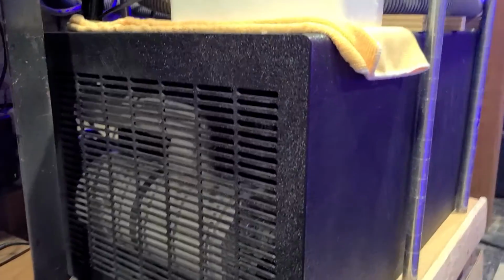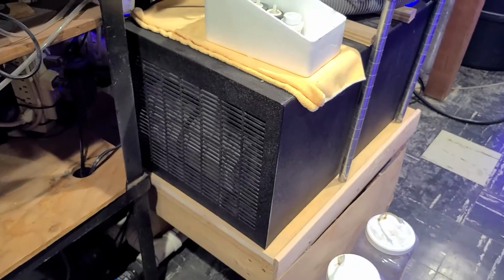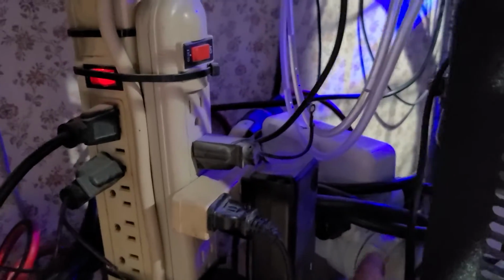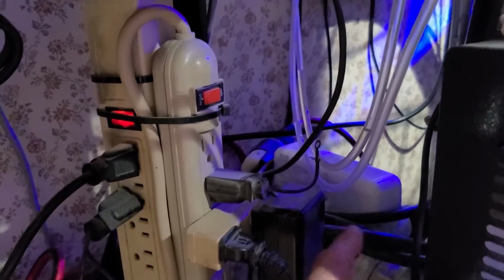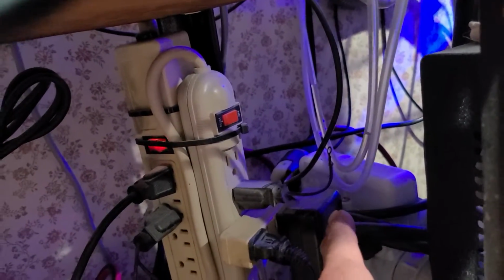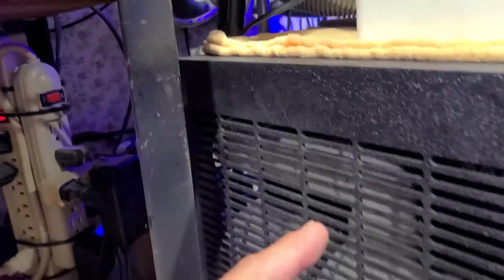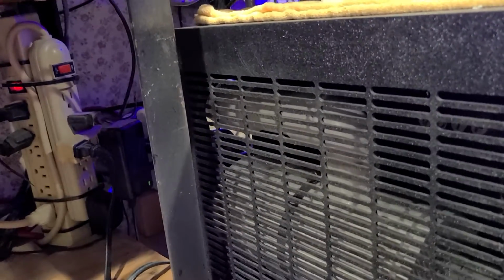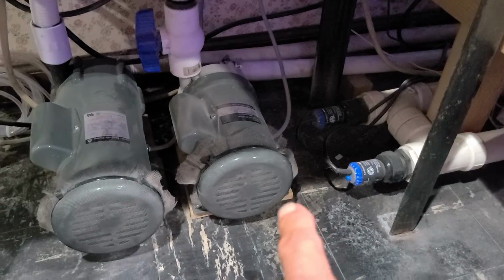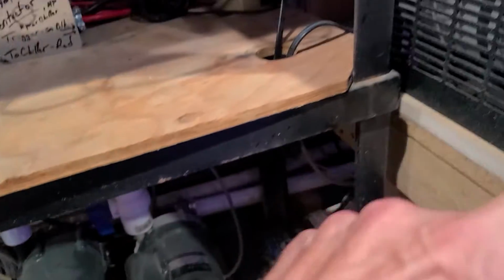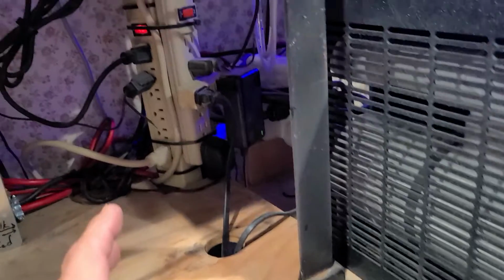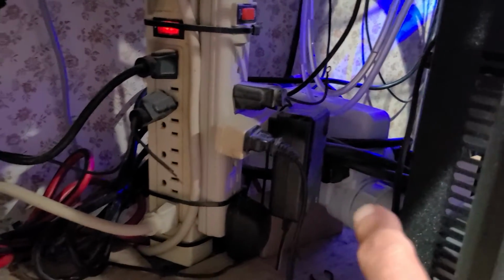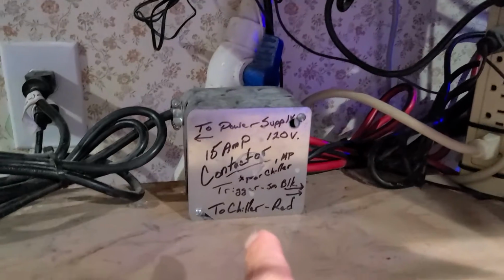So I'm running, like I said, a half horse chiller, and I also recommend using what they call a flow switch, and that's this guy on the back of here. It's connected to the chiller. Water runs through it. If there's no flow, basically it turns your chiller off, so you don't freeze the guts inside the chiller and destroy your chiller should your pump fail to run. So if there's no circulation, the chiller doesn't run, doesn't freeze up, bust. So preventative measures: always use a flow switch and use a lighting contactor.